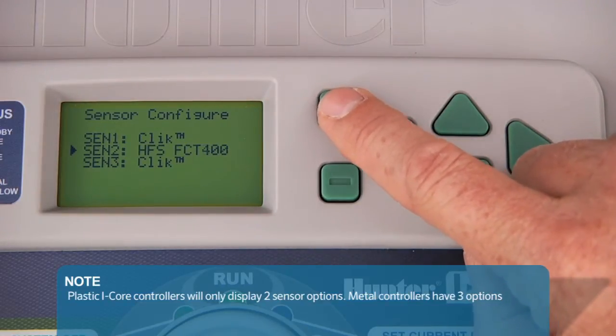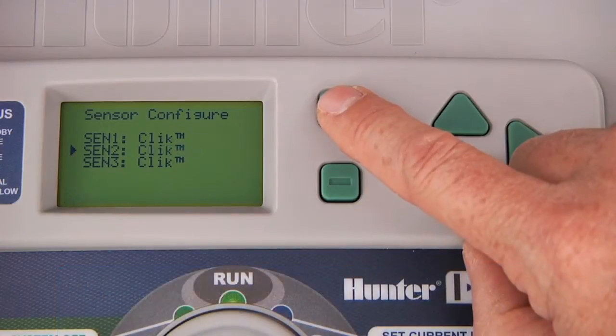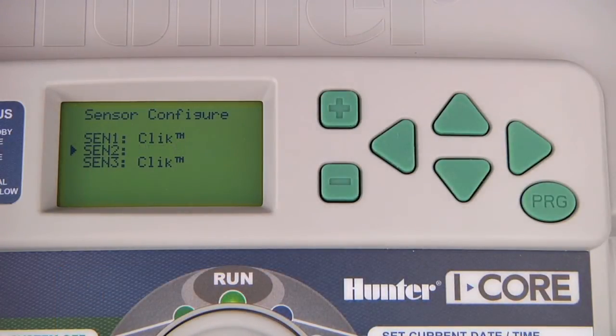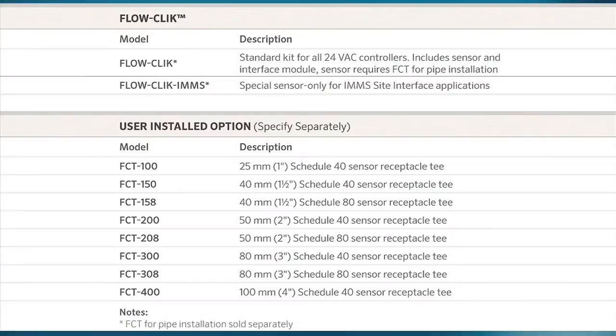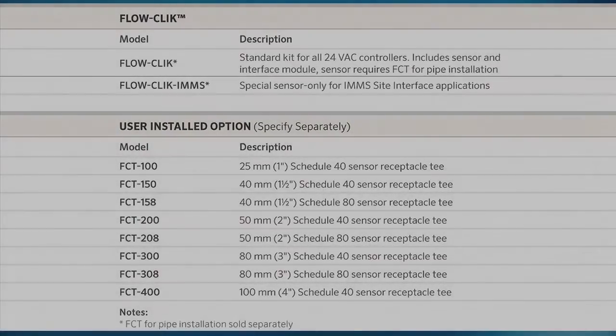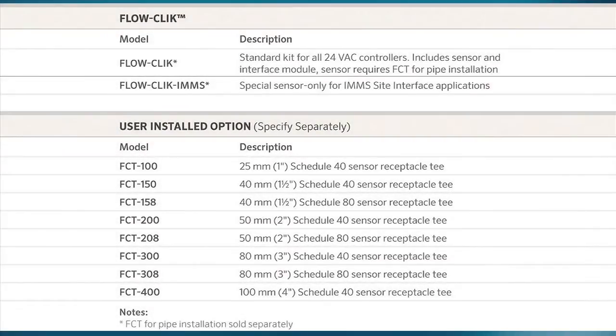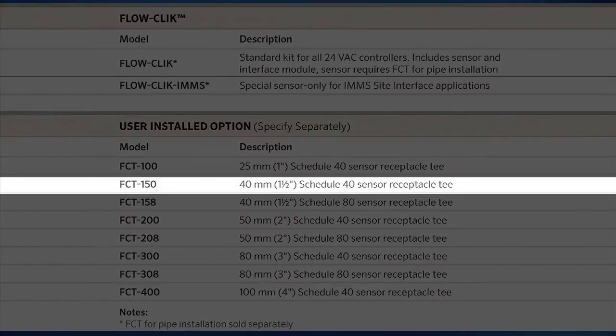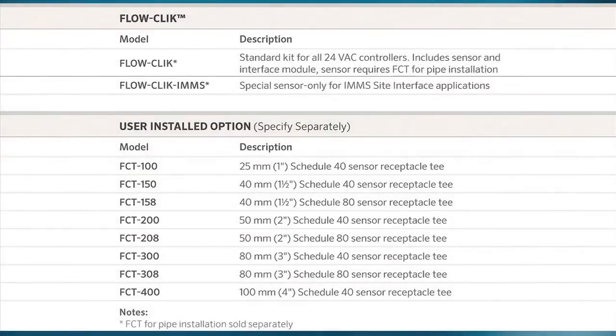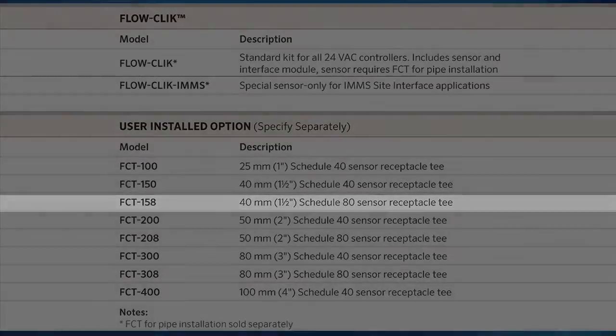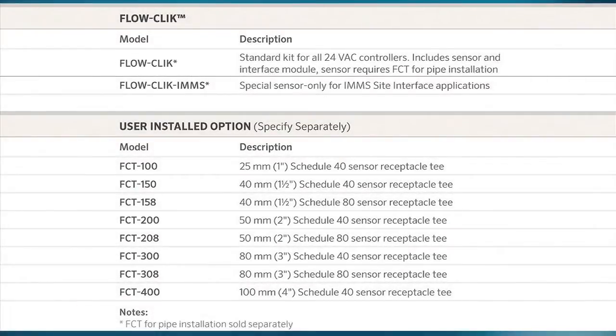Notice that we can choose among different flow sensor options depending on the size of the fitting. For example, if you are using a 1-inch Schedule 40 sensor body, then you would choose HFS FCT 100. If you are using a 1.5-inch Schedule 40 fitting, then you would choose HFS FCT 150. For a 1.5-inch Schedule 80, you would choose the HFS FCT 158, and so on. You can check the owner's manual for a complete list of sensor options.